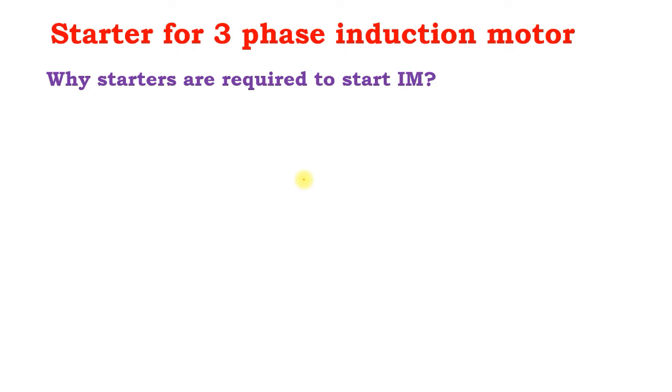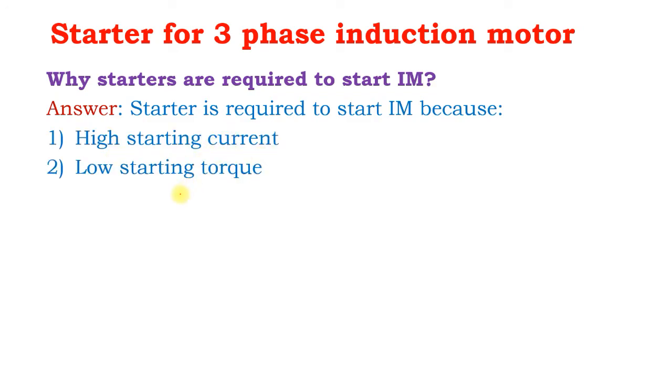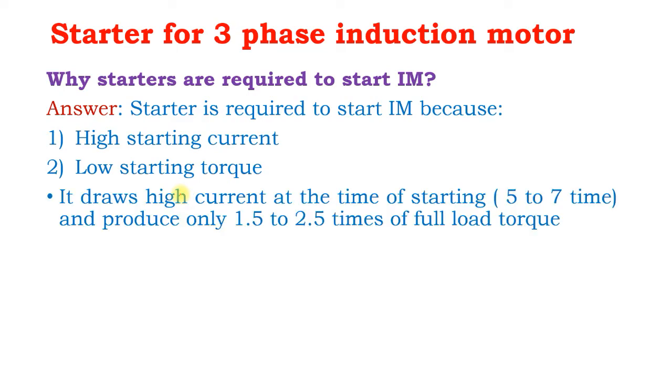Starter for three-phase induction motor. Why are starters required to start an induction motor? To prevent high starting current and low starting torque. So what happens in the standstill condition? Before starting, the motor is in standstill condition. In the standstill condition, the rotor frequency and stator frequency are both the same. Therefore, the stator will carry more current, which might be in the order of 5 to 7 times its full load current. Due to this high current, the torque is only 1.5 to 2.5 times.